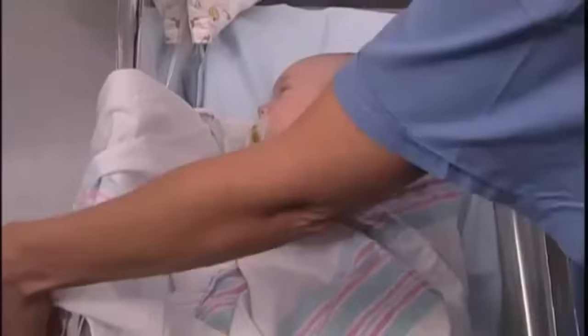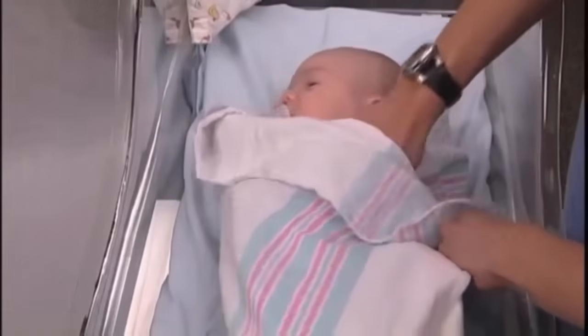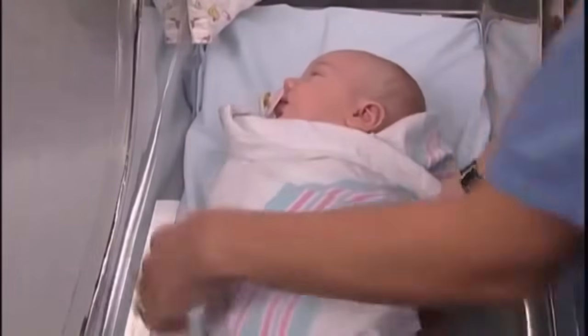The best time to perform your testing is when the infant is sleeping. If this is not possible, a pacifier may be used to calm the newborn. You should be aware, however, that the sucking action will add noise to the test and decrease the likelihood of a passing result. When the newborn is calm, begin the test. Swaddling the infant in a soft blanket can help prevent unwanted noise caused by the baby's movements, as well as minimizing the chances of the probe being pulled out of the ear canal during the testing process. As you can see, the process of testing a newborn is much easier when using the external probe.